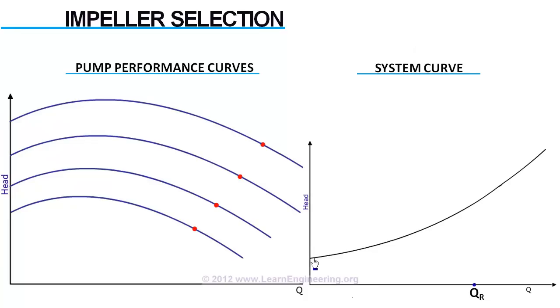Depending upon minor losses and major losses in the network, it would vary like this. Please note that system curve will change drastically, depending upon valve opening. Assume this is the system curve at a particular valve opening. Required flow rate is marked here.